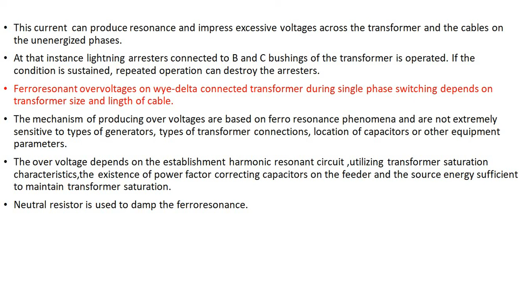Ferroresonance overvoltages on Y and delta connected transformers during single phase switching depend on transformer size and the length of cable. The mechanisms producing overvoltages are based on ferroresonance phenomena and are not extremely sensitive to the type of generator, type of transformer connection, location of capacitor or other equipment parameters. The voltage depends on the establishment of a harmonic resonance circuit utilizing the transformer saturation characteristics, the existing power factor correcting capacitors on the feeder, and a source of energy sufficient to maintain transformer saturation. A neutral resistor is used to damp the ferroresonance. Thank you.